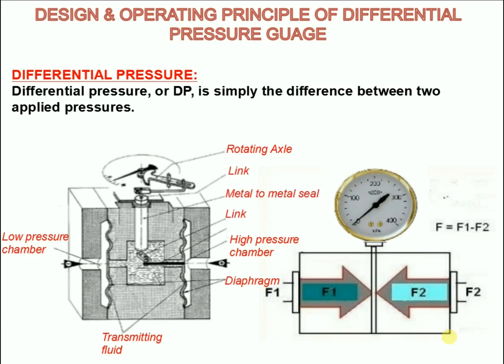A pressure greater than the full scale will close the valve, thus discontinuing the transmission of pressure. Both diaphragms rest on a liquid cushion that allows the instrument to withstand process pressure up to the maximum pressure rating of the instrument.